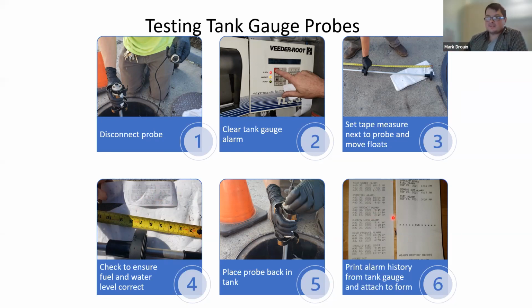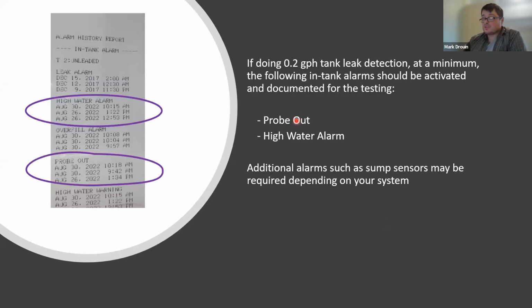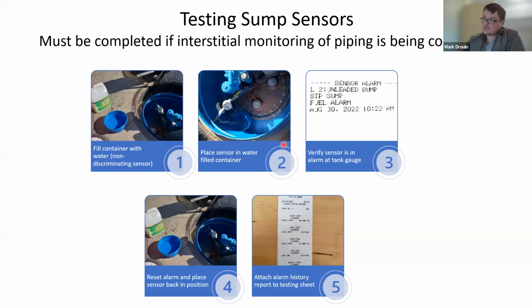So, this isn't the whole procedure. Again, I'm just trying to summarize quickly what you may see out in the field. Now, with these alarm history reports, for this specific Veeder-Root system, one of the things we're going to look at is making sure this testing was done per one of the methods, and every method calls this out. In that previous example, as we disconnected that probe, it went into alarm. That tells us that that day, at least, that probe was disconnected. And we also saw that they raised the float, and then the high water alarm went in. So at a minimum, we know those two things were done. Those are two things specified in our documentation, the PEI and the Veeder-Root document. So we're confident this was done correctly. That's one method, to test a probe. Here in the same facility, we tested a sump sensor.